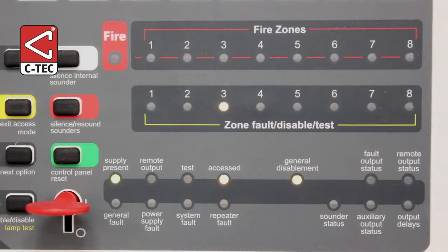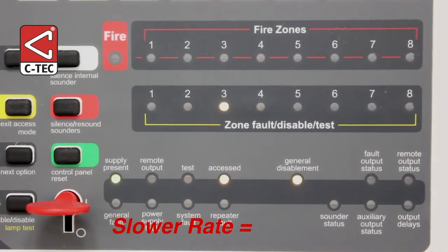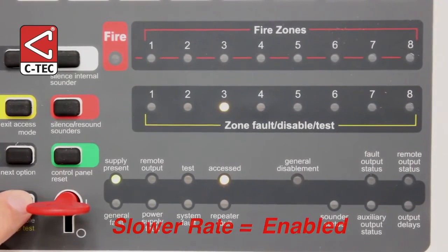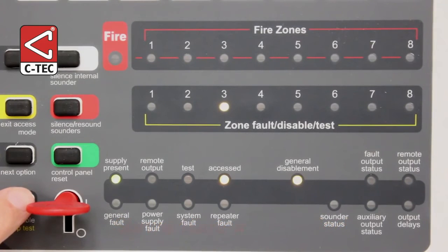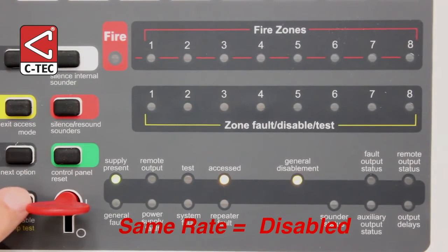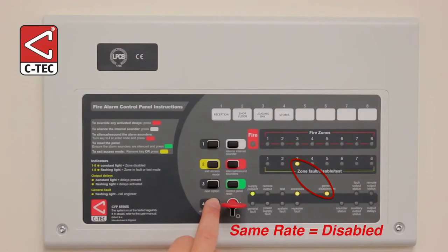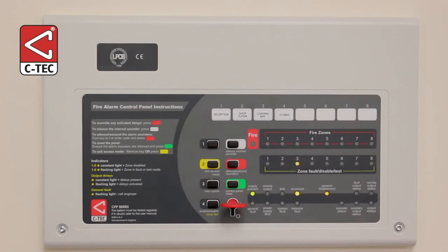If it flashes slower than the general disablement light, its current status is enabled. If it flashes at the same rate, its status is disabled. Press the Enable Disable button to toggle between enabled and disabled. As we want to disable Zone 3, we need to make sure the two lights are flashing at the same rate. To confirm the selection, press the Next Option button.